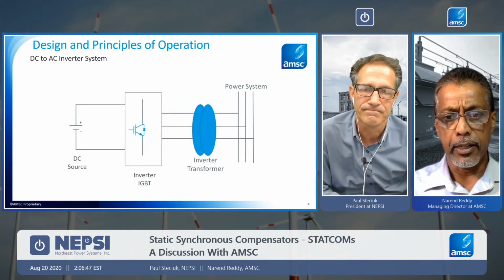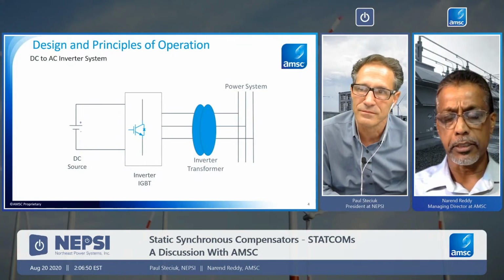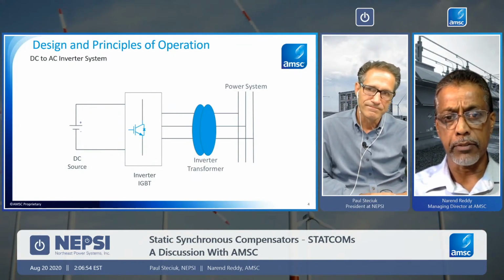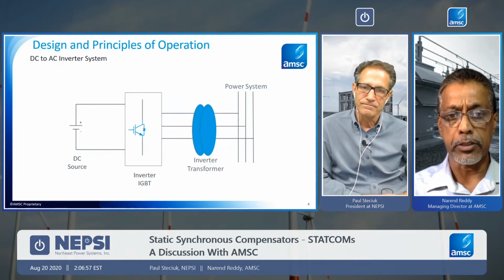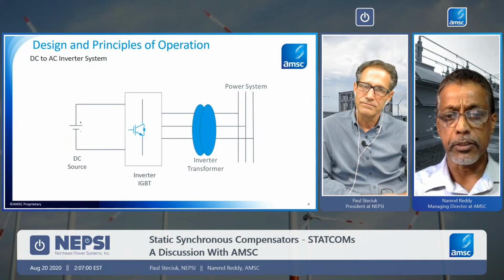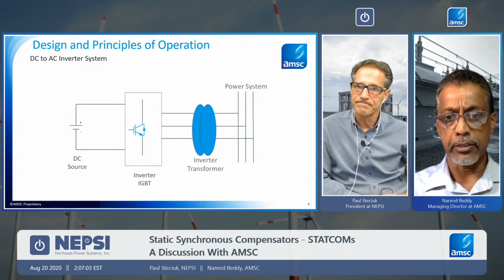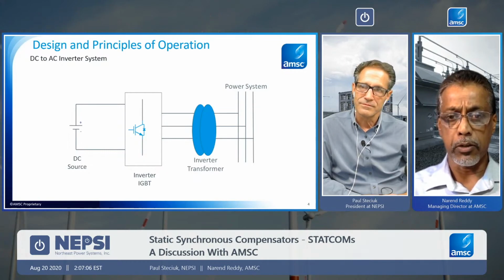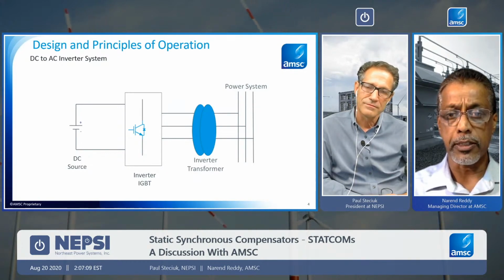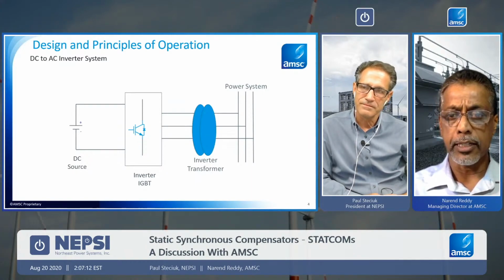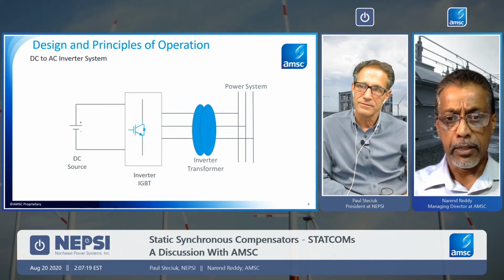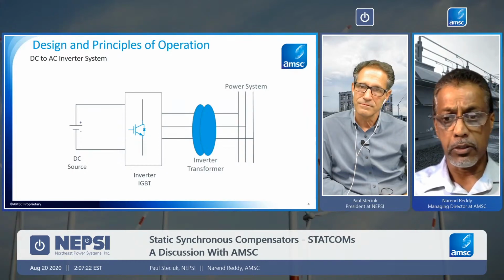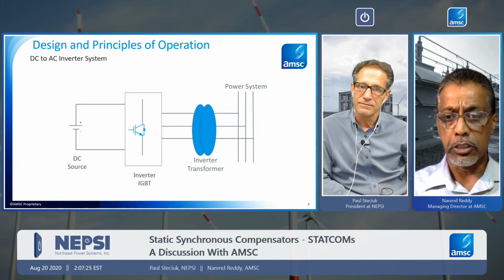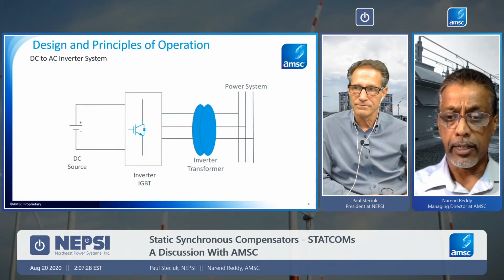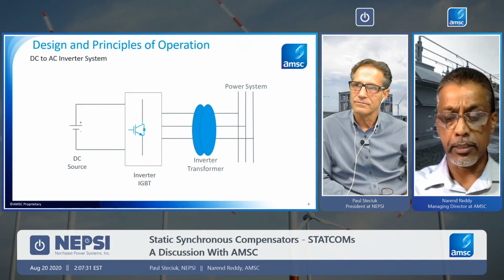At the most basic level, the main components of an inverter system for a STATCOM are a DC source, which is some DC capacitors that maintain the DC bus voltage reference. You have some IGBTs that are connected in a certain configuration, and they are switched depending on the current or the amount of control that's needed. And then those inverters are connected to the AC grid via a step-up transformer. This could be taking a 400 volt, 480 volt, or 3 to 35 kV range inverter up to medium voltage or even higher, depending on where the application of this STATCOM is required.